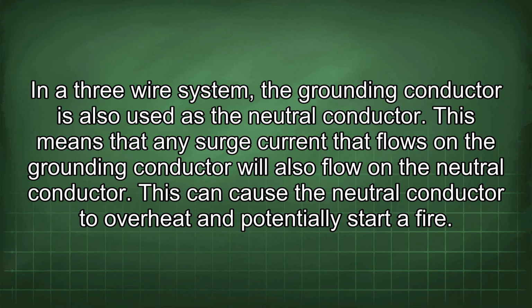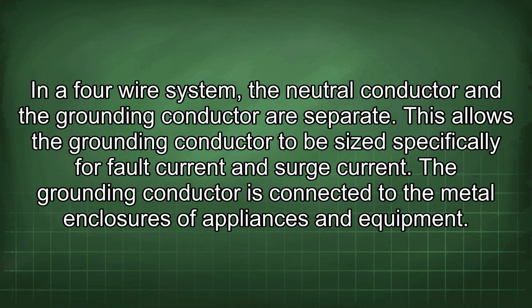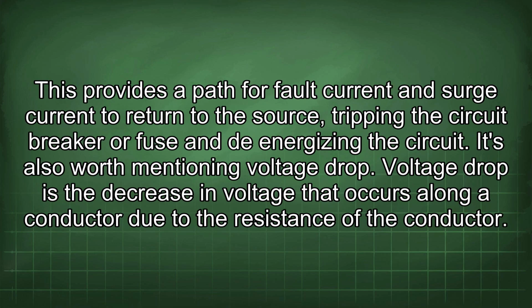In a 3-wire system, the grounding conductor is also used as the neutral conductor. This means that any surge current that flows on the grounding conductor will also flow on the neutral conductor. This can cause the neutral conductor to overheat and potentially start a fire. In a 4-wire system, the neutral conductor and the grounding conductor are separate. This allows the grounding conductor to be sized specifically for fault current and surge current. The grounding conductor is connected to the metal enclosures of appliances and equipment. This provides a path for fault current and surge current to return to the source, tripping the circuit breaker or fuse and de-energizing the circuit.